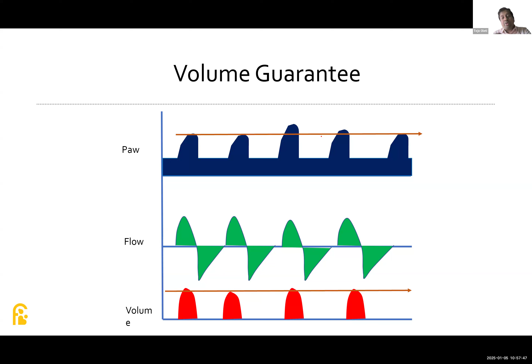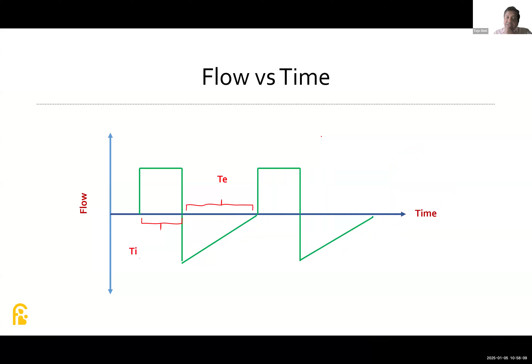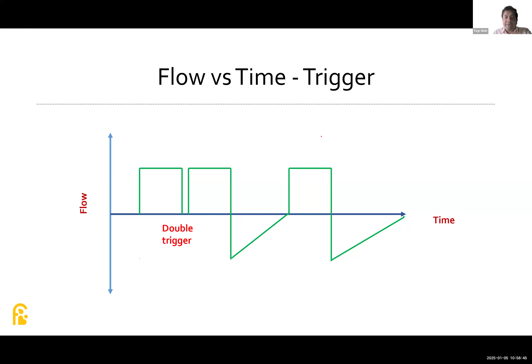What are the other uses that we wanted to look at? In this, what happened here compared to here? The baby wanted to take a breath here, but it was not supported. So in the initial graphic, you have seen only a mechanical breath. Suppose we have a trigger which is good, then it could have delivered a complete breath. What happened in this graphic now? There are double inspiratory cycles. It is due to a double trigger, might be due to water in the circuit, or the baby having too rapid a respiratory rate. That's the reason you are having the double trigger here.